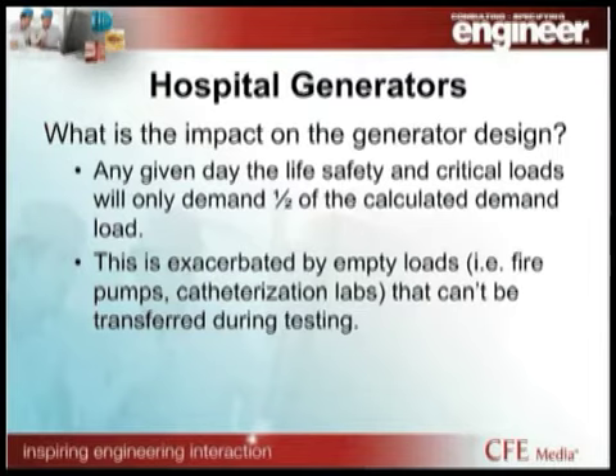A lot of times ORs, cath labs, and that, you're not going to test those transfer switches during the testing. So what we end up with, certainly from the facility engineer's perspective, is that the generator looks oversized. The generator is only seeing 25-30% of its capacity tested each month, and that's hard on a large diesel engine because when they're in those low ranges, they pass a lot of oil into the exhaust. That's the term wet stacking. And if that temperature doesn't get up high enough in the exhaust manifold, it actually shortens the life of the generator itself. So by testing it, you're shortening the generator's life.